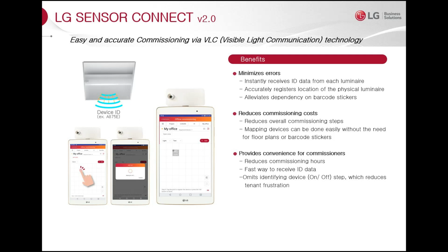So this is essentially us getting the barcode ID from the light without requiring barcode stickers. Previously, having barcode stickers properly mapped out was a difficulty. There is user error by the installers, and there's also user error by the commissioning agent when entering those IDs into the app and making typos. Now there's no barcode stickers in the wrong spot, and no more typos, because you've got the light you're standing right underneath.